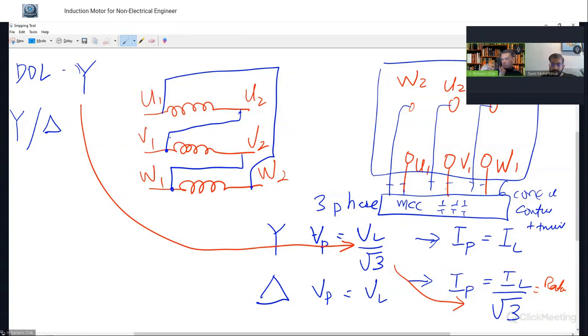One is maybe you are using an auto transformer. But an auto transformer requires area, area to put in, where to put in the transformers and everything. Then the panel will become bigger. Then you go for another solution, maybe star delta. Star delta requires a bigger controller than DOL, but it is much smaller than an auto transformer. So maybe they go for star delta.